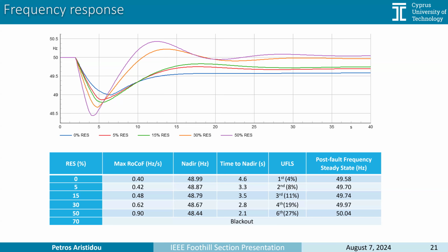Is it coming from the natural response of the battery and its converter, or can you comment on that? These are grid following technologies. So they have a PLL and they measure the frequency, and they need several cycles to measure the frequency and to get a good estimation of the RoCoF. Then there is the computation time, and then the ramp-up time of the units. These are cheaper technologies, so they are not the same as grid forming technologies. The activation between 500 and 800 milliseconds is considered the standard for these sorts of technologies in Europe.